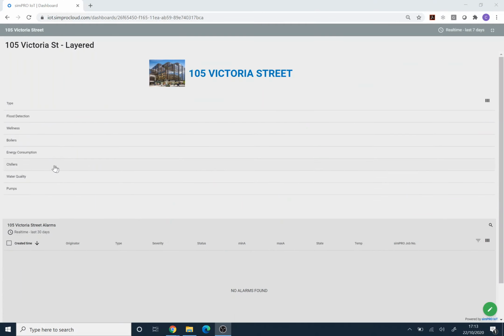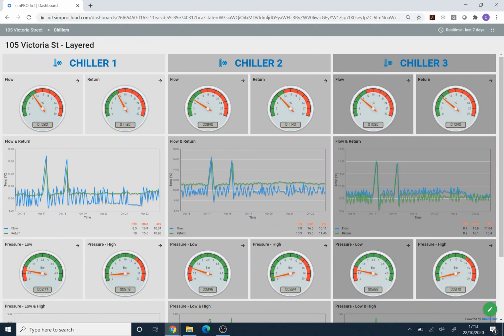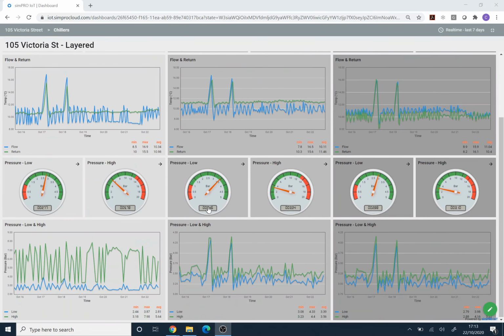We also have a similar setup for the chillers. With flow and return temperatures plotted against each other for easy analysis, along with also the current values. In addition, we have also installed our dedicated refrigerant pressure monitors, which again provide current and historical values. The IoT pressure transducers, again running on battery, provide the measurements and are affixed to the high and low circuits of the equipment. These sensors provide early warnings of possible refrigerant leaks for compliance and performance purposes.